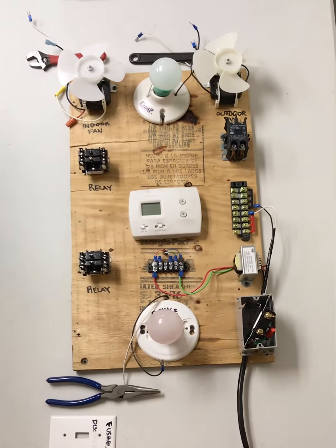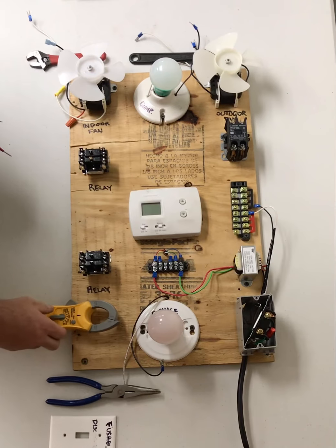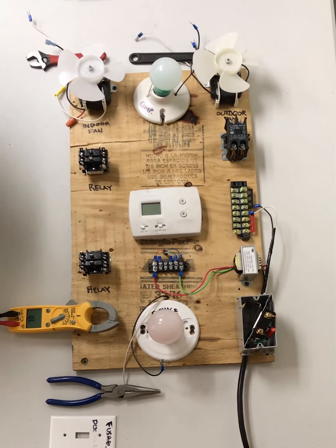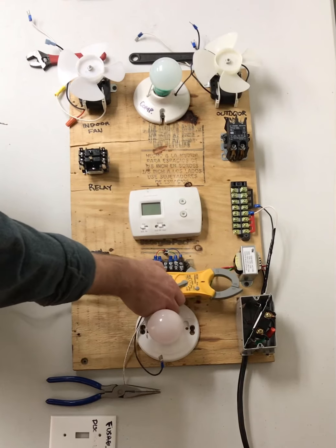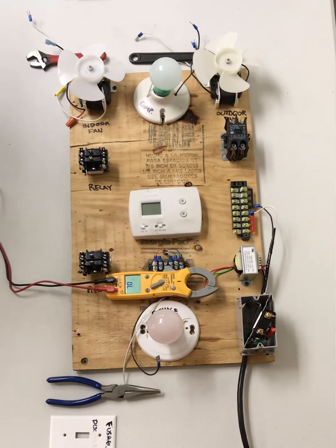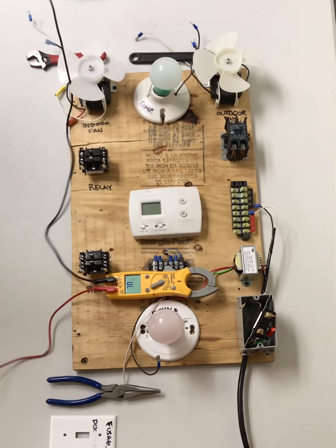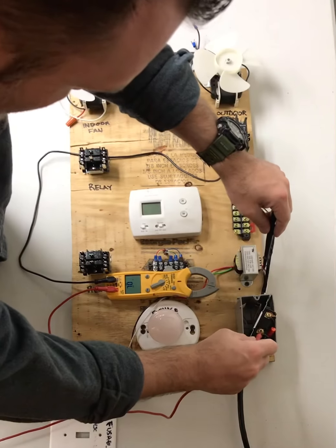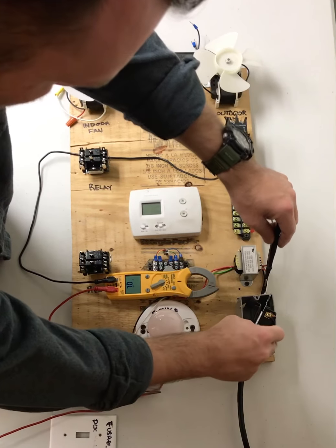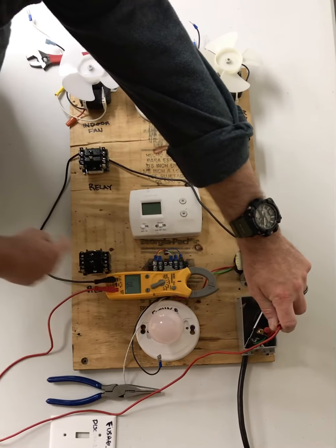So one way we can test it, like I said, to see if our switch is good, is again, we go to continuity. Move this up here so you guys can see it a little better. And we take our probes and we put one probe on the incoming and one probe on the outgoing side of the switch. Now, right now, our switch is off. So we should get nothing. If we put a probe here and we put a probe here, we get nothing. No beep. We're reading OL on our meter.